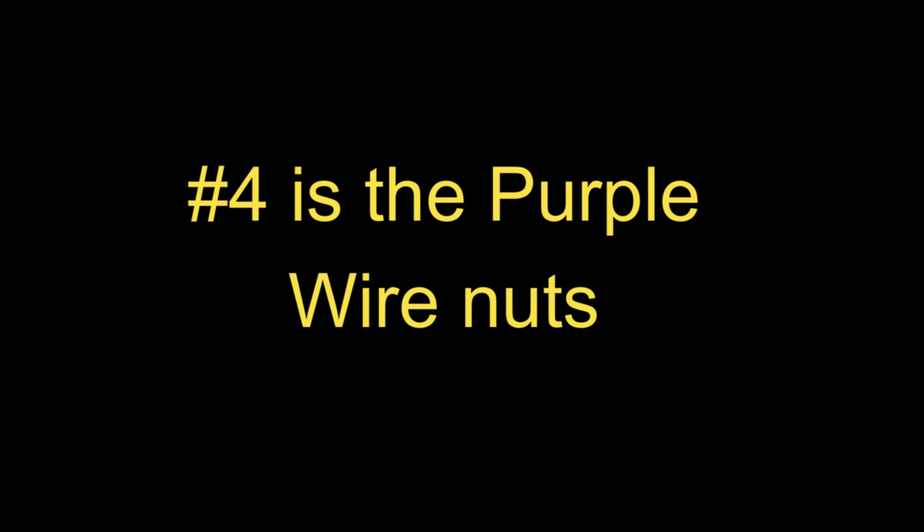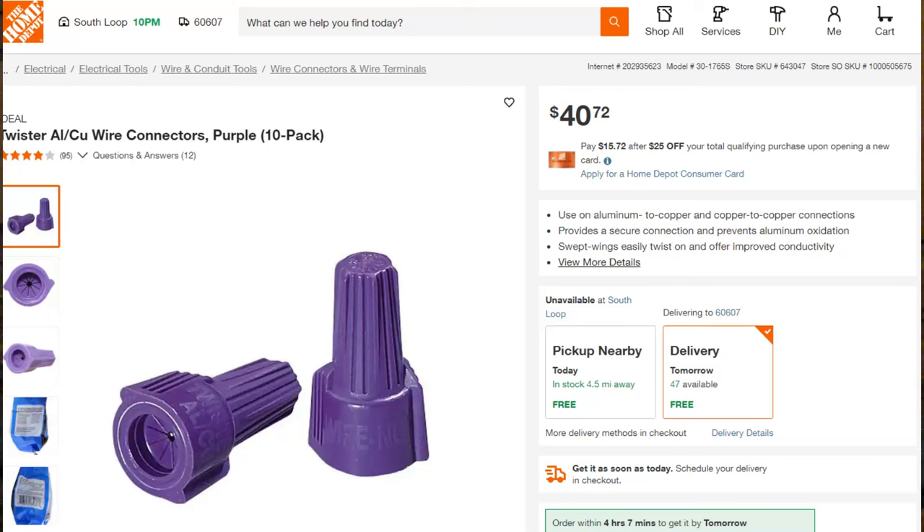There is a fourth connection that is accepted by the National Electrical Code — if it's a UL-listed product — and that is the purple wire nuts. According to the manufacturer, the purple wire nuts have a special grease inside and are made with a special wire for the springs that does not expand and contract like standard wire nuts. Whatever you do, do not use the yellow, red, or gray wire nuts on aluminum wiring.